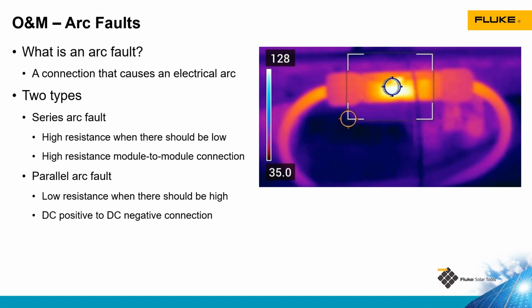The second arc fault is a parallel arc fault. And this is the opposite. It's where I have low resistance when I want high resistance. An example here would be a DC positive making connection to a DC negative. They should be separated, but for some reason they rub together, and now the positive and negative are making a connection. In both of these situations, the electricity is arcing between the 2 sides, either across the high resistance connection or across the low resistance connection between 2 conductors.